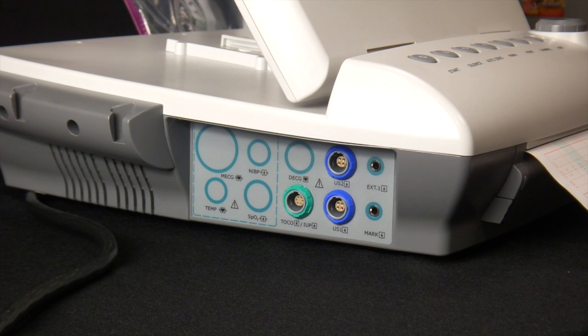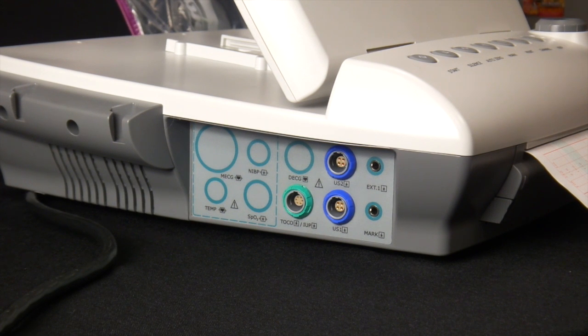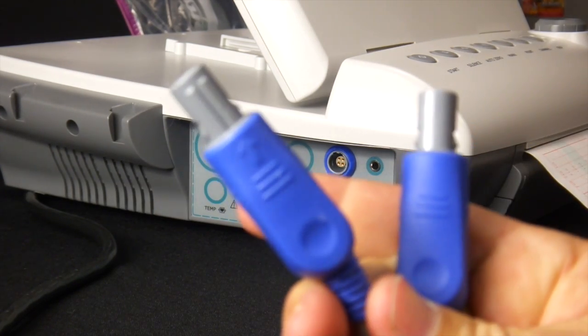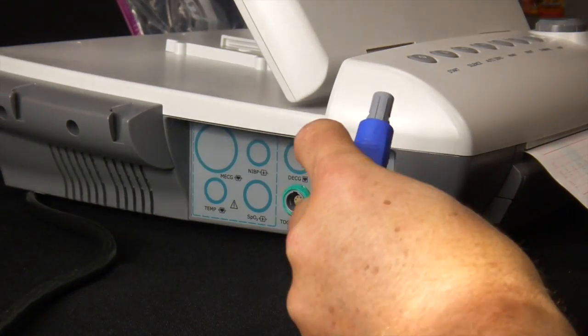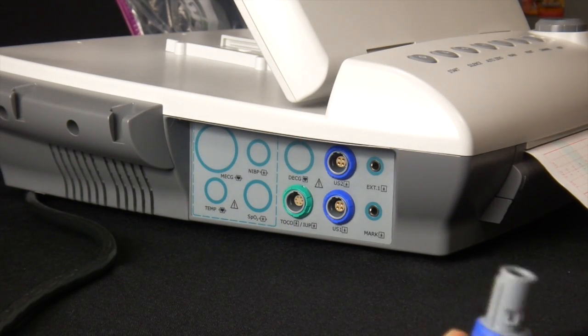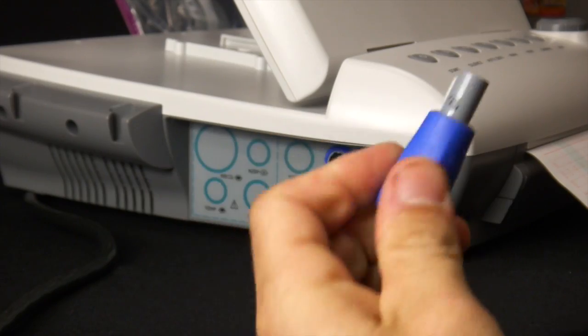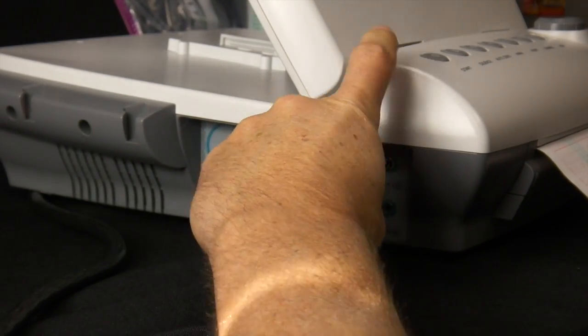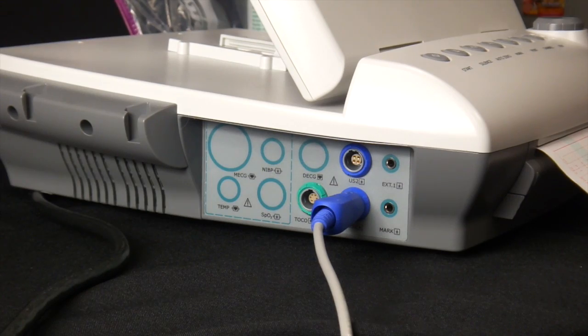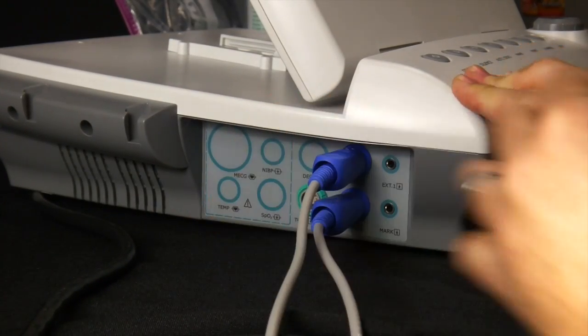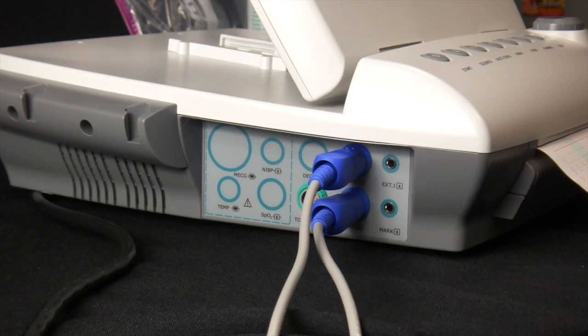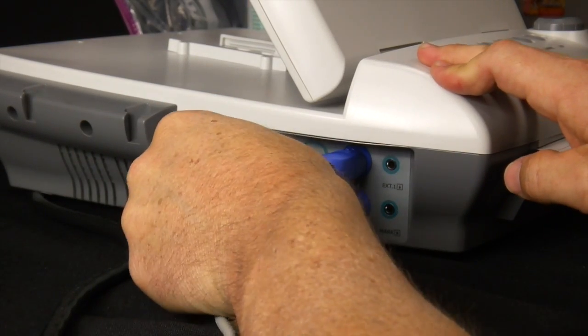We're now looking at the left side of the monitor. We'll show you how to plug in and remove your transducers and sensors. Very simple, and each is color coordinated. The blue fetal heart rate transducers have blue LEMO connections on the side of them. They will each plug in and they're keyed. There are 2 keys on the top here. You can see they go on the top of each connection. That's ultrasound 1. Here's ultrasound 2. And then to the left of that in green is the TOCO transducer.